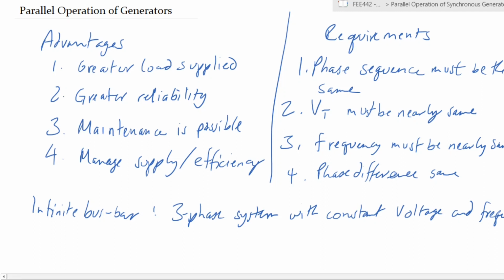Right? This is because you have systems that have so many supply generators and so many loads that the voltage and frequency are extremely stable, such that the addition of one more generator would not make a difference to the voltage and the frequency. As we will see going forward, you remember we talked about voltage regulation. That is when a generator is supplying a load.